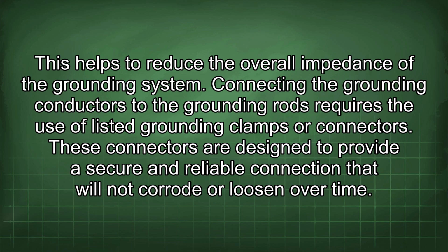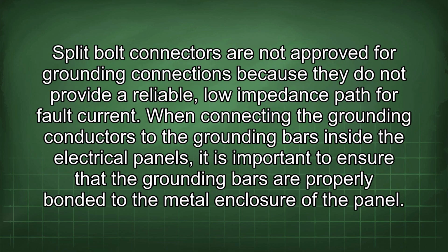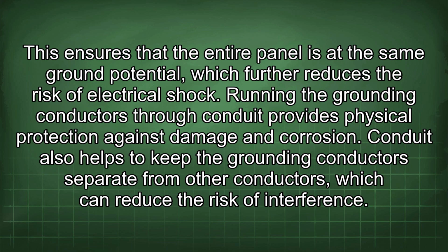Connecting the grounding conductors to the grounding rods requires the use of listed grounding clamps or connectors. These connectors are designed to provide a secure and reliable connection that will not corrode or loosen over time. Split bolt connectors are not approved for grounding connections because they do not provide a reliable, low impedance path for fault current. When connecting the grounding conductors to the grounding bars inside the electrical panels, it is important to ensure that the grounding bars are properly bonded to the metal enclosure of the panel. This ensures that the entire panel is at the same ground potential, which further reduces the risk of electrical shock.